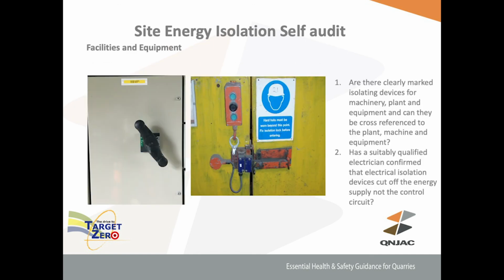So a couple of photographs of facilities and equipment. Question 1: are there clearly marked isolating devices for machinery, plant and equipment, and can they be cross-referenced to the plant, machine and equipment? It's quite straightforward, and on the vast majority of occasions you see equipment isolators clearly marked to the equipment they isolate. Second question: have suitably qualified electricians or electrical engineers confirmed that electrical isolation devices cut off the energy supply and not the control circuit?